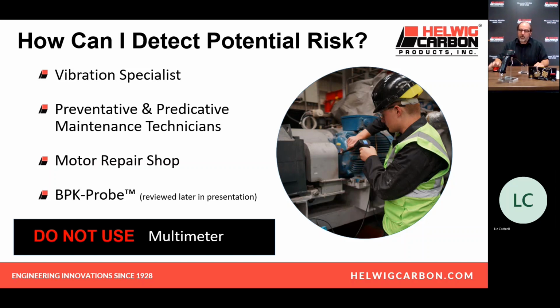Encourage your motor repair shop to open up your motor, look at the grease, cut the bearings, look at the bearings. Let's find out what the source of your failure was. Let's not just put a new bearing back on there or have somebody talk you into isolated or insulated bearings. Let's not do that. It's a lot of expense. It's unnecessary, and it's probably not the right thing to do. Let's just make sure it's right.